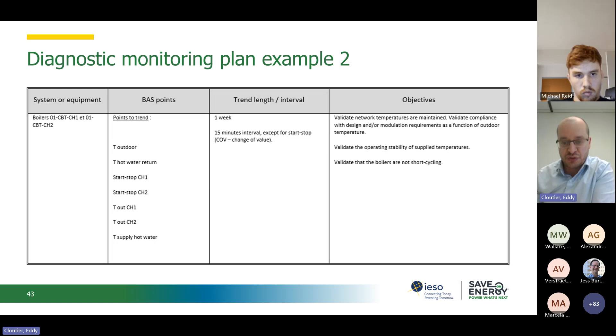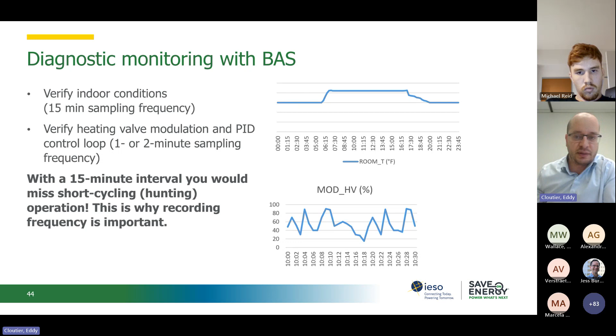Just a quick example of why we want to adjust the measurement frequency depending on the objective. The first graph at the top of this slide, we want to verify the indoor temperature conditions. Usually for such measurements, 15-minute sampling is more than enough. And the second one is to validate or verify heating valve modulation and PID control loop. And in that case, of course, the frequency of measurement needs to be much more rapid, I would say. If you were to try to do this analysis with a 15 minute interval, you would probably miss short cycling. And this is why determining the correct frequency of measurement is important depending on the objective.